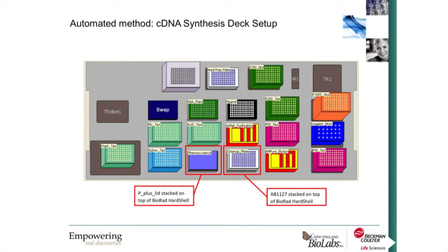This is a picture of the cDNA synthesis deck setup. We have a 96-channel wash station, an orbital shaker under one plate, our integrated T-Robot on deck, a static Peltier to maintain master mixes at 4 degrees, and various ALPS. This deck is reflected in the deck setup of our Biomek FXP behind me. If doing on-deck thermocycling, the method will add a stackable lid to the plate for thermocycling. If not, that labware is eliminated from the deck setup. To its right, we have an AB-1127 plate stacked on top of a BioRad hard shell.